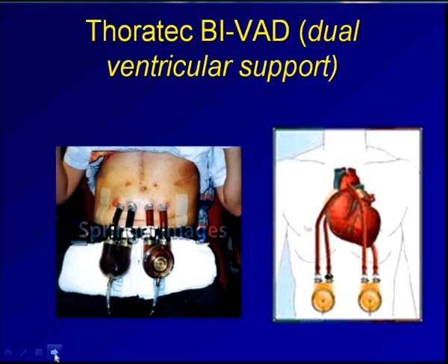The picture on the left, obviously, if you were to do a patient assessment on a patient like this would be pretty much graphically overwhelming to see, because this is not something we would normally see from a patient. But obviously, their pumps are outside the body. That blood flow, obviously, on the left is venous and on the right is arterial, and that is something key for us to be able to assess whether the device is working properly or not, is you'd be able to actually shine a flashlight or a pen light into those pumps and actually see the blood flow coursing through the pumps.